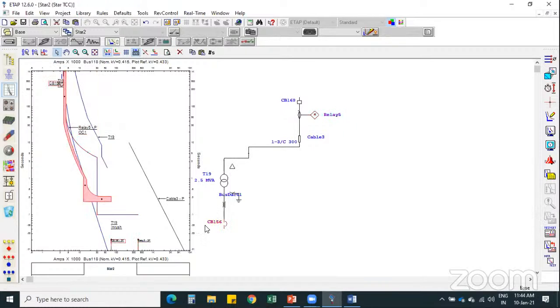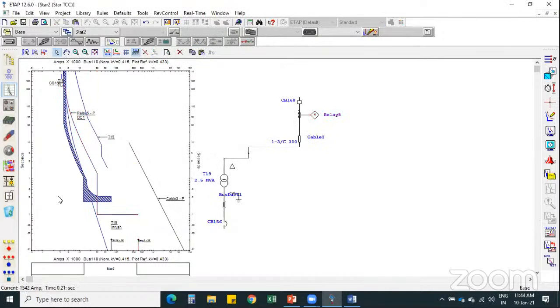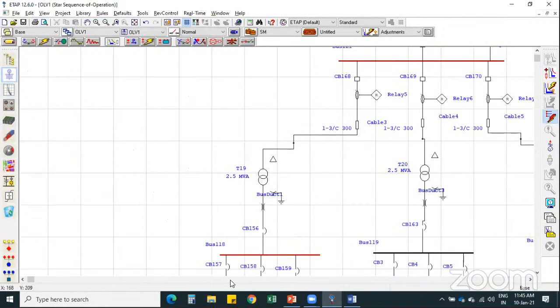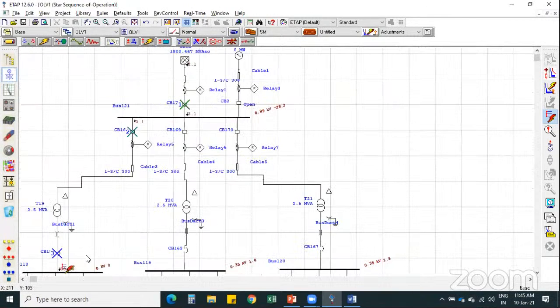In order to coordinate this LVCB with upstream, we need to change the curve. We will only change the curve for extremely inverse section, and we will adjust the TMS value. Okay, and the through fault condition also we need to check. The through fault I am talking about means, you can see this is the fault current value for this circuit breaker. If any fault occurs in LV section, then this relay should not operate first. But for any fault condition, we can see this relay is getting tripped first, right? For any fault in HV section, the incomer relay is tripping first, then circuit breaker 2 is tripping second, and if a genuine fault occurs, the circuit breaker is tripping last. So the system is not properly coordinated.